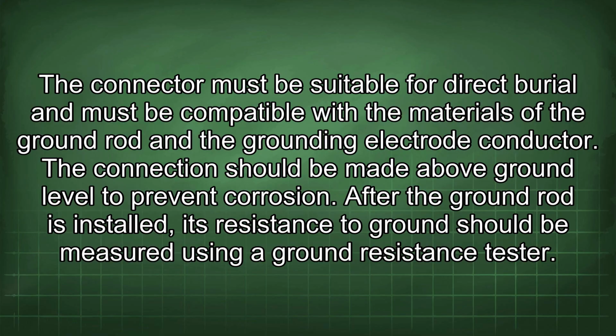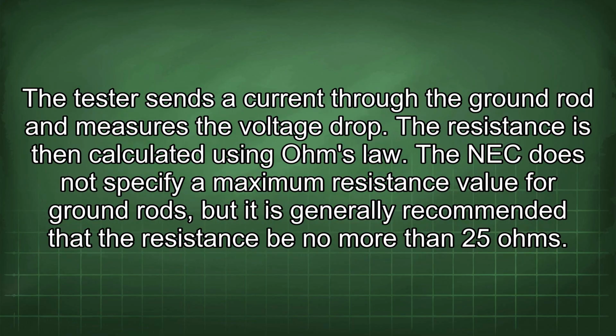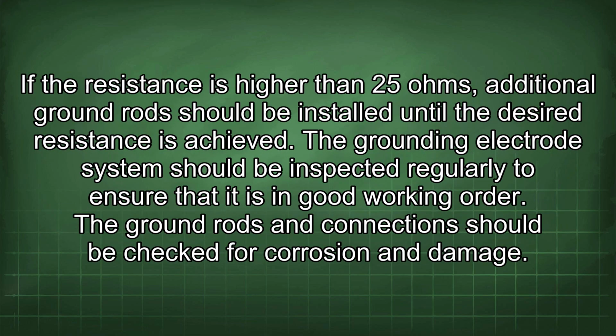After the ground rod is installed, its resistance to ground should be measured using a ground resistance tester. The tester sends a current through the ground rod and measures the voltage drop. The resistance is then calculated using Ohm's law. The NEC does not specify a maximum resistance value for ground rods, but it is generally recommended that the resistance be no more than 25 ohms. If the resistance is higher than 25 ohms, additional ground rods should be installed until the desired resistance is achieved.